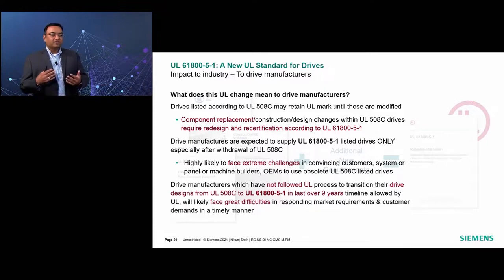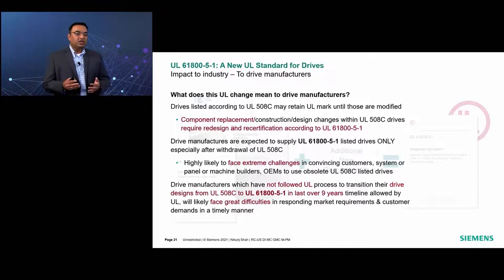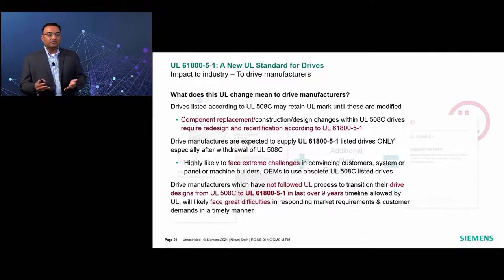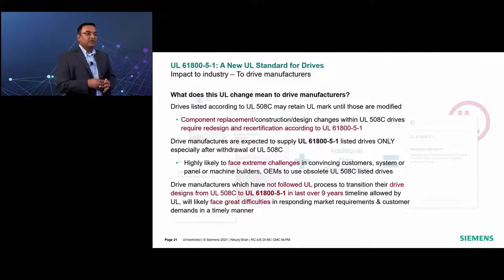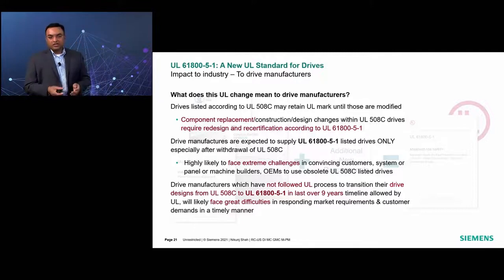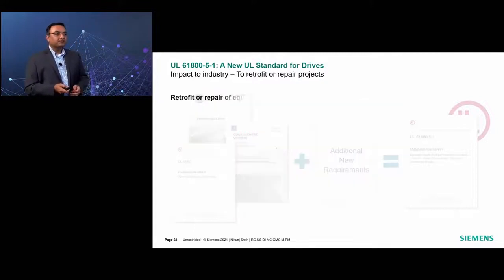These are the drive manufacturers which have not followed the UL process of transitioning the drive products from the old 508C to the new 61800-5-1 in the last 9 years, which is allowed by UL in agreement with all the manufacturers. They will likely face great difficulties in responding to the market requirements and customer demands in a timely manner to supply drives listed according to the new UL 61800-5-1.